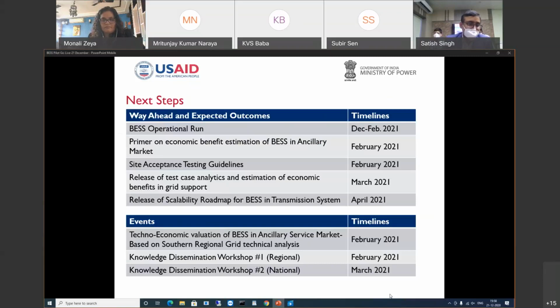Then, site acceptance testing guidelines. This is a very important document now, because we were developing these applications perhaps for the first time in India, and there was no specific guidance on what parameters should be tested, how the battery capacity test should be done. So starting from basics to the advanced level, we say it is not that you only test on the extreme values, you test on the probable values where your batteries might not provide the anticipated responses. All this, in consultation with Power Grid and support from our grid integration advisor DNVGL, plus also KC International, we have drafted the guidance note.